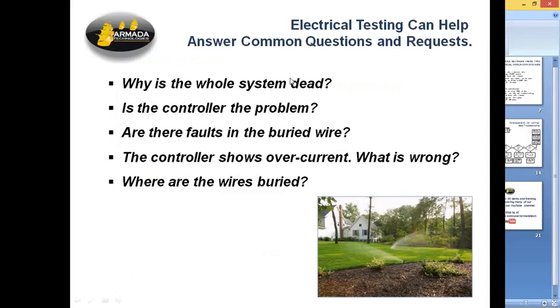Is the system dead? And why is the system dead? Is the controller the problem? We always say in the troubleshooting end of this stuff, and I have a chart to illustrate this a little bit later, you always start out at the source of the power and work toward the field. So you're always looking first at the controller. If somebody's popped the circuit breaker and the controller's dead, or someone's got a rain sensor unplugged, who knows, but the controller can stop working. These are all things that you need to check that are in common with any irrigation system.